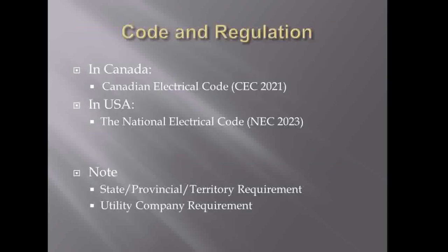So what code and regulation do we need to follow for the load calculation? In Canada, we follow the Canadian Electrical Code, the CEC 2021 version. In the United States, you should follow the National Electrical Code. You also need to check state, provincial, and territory requirements, as different provinces may require different things. Also check with the utility company to see if they have additional requirements.